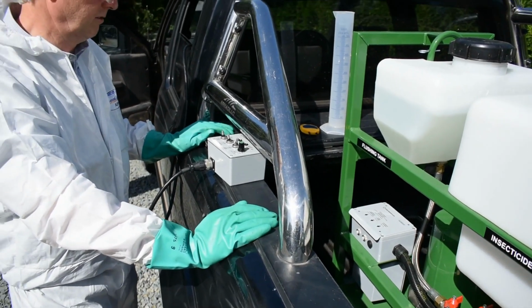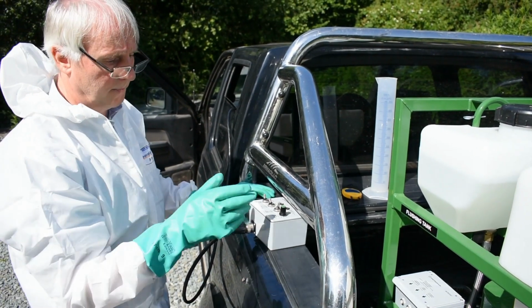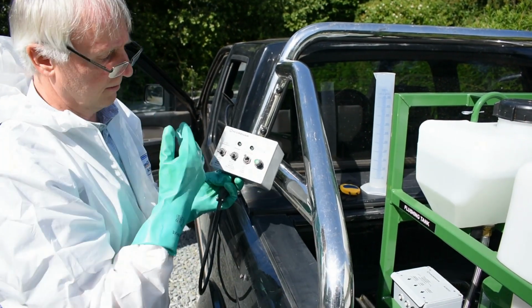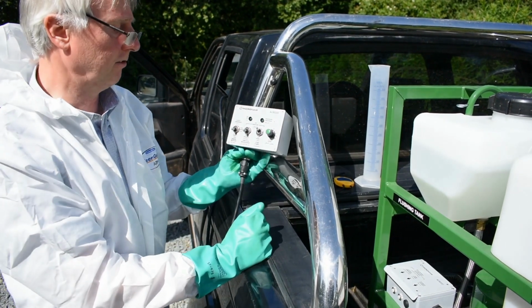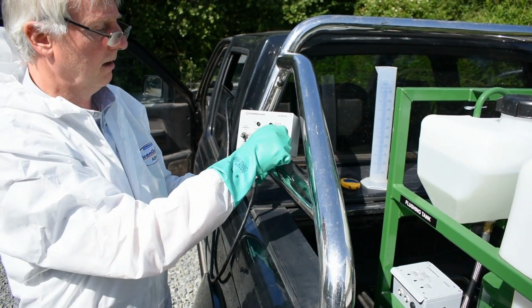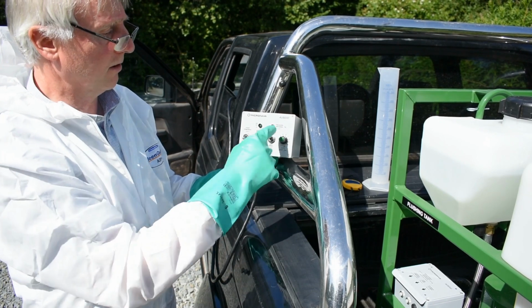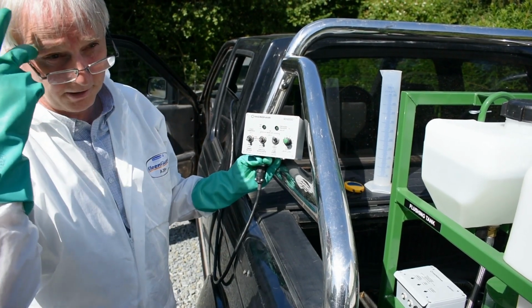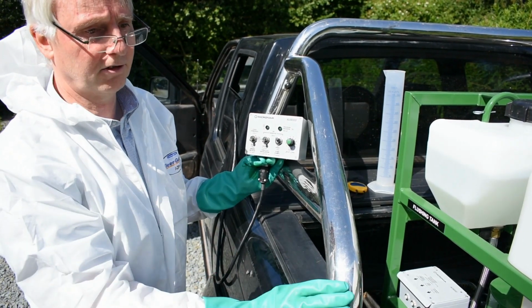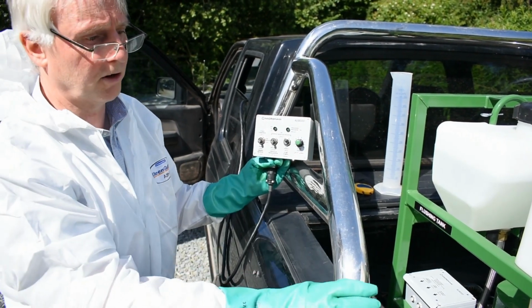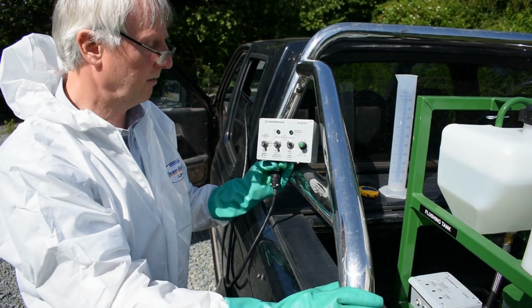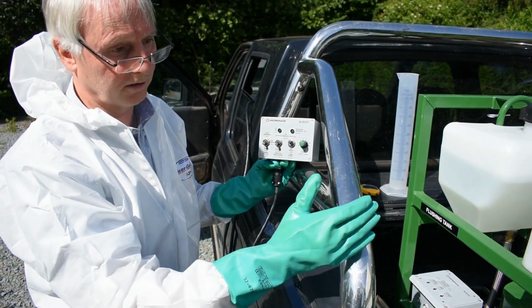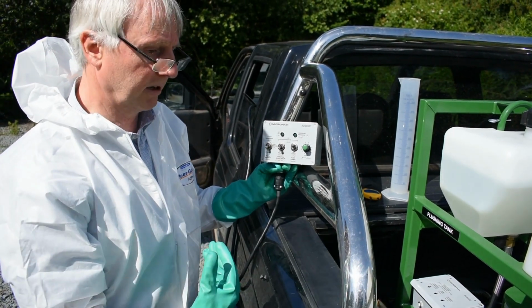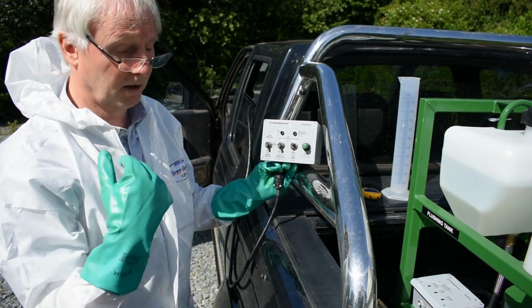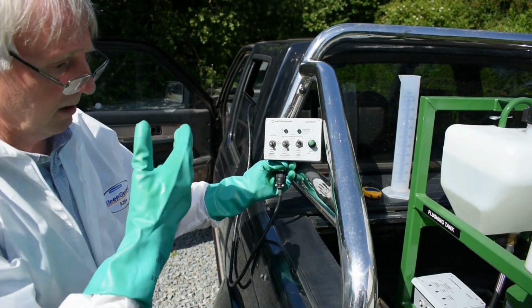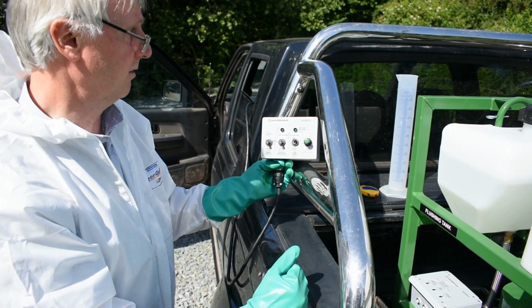Okay, so we're just going to look at how you calibrate the flow control. I've removed it from the cabin just for purposes of demonstration. Normally, it's really not necessary to calibrate because it's pre-calibrated for the operator. So this would only be an occasional check you would do. You have to do it with the product mix, hence why we've got gloves, although in reality I'm just using water today to demonstrate. But if you were working with chemical, you've got to have the appropriate protective clothing, a face shield, gloves and all these things.